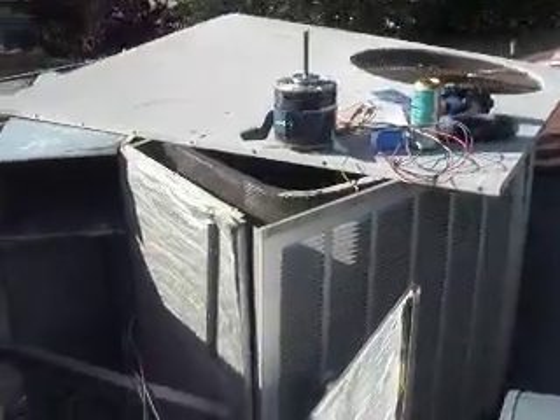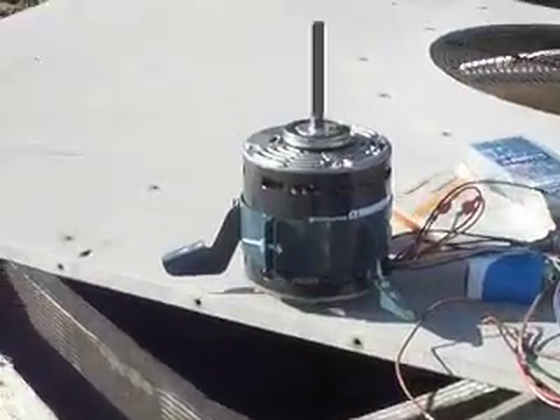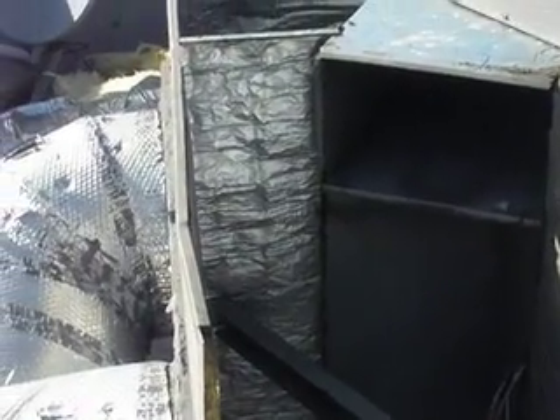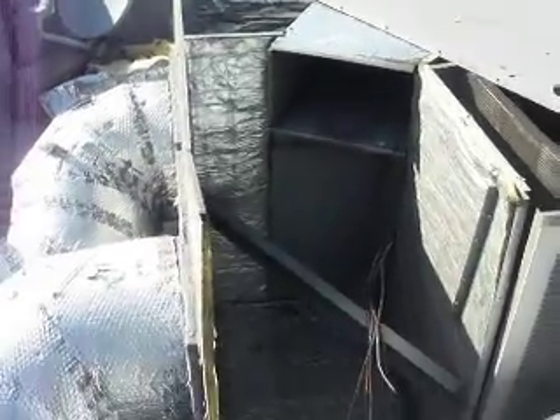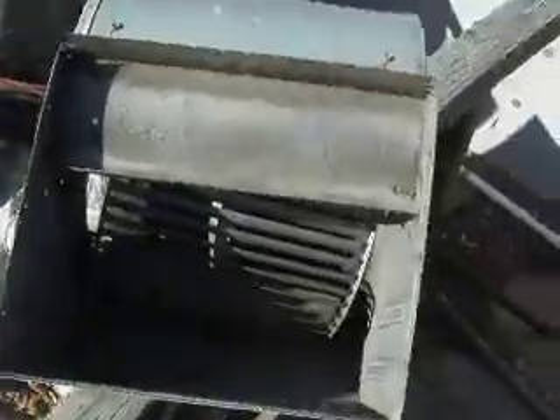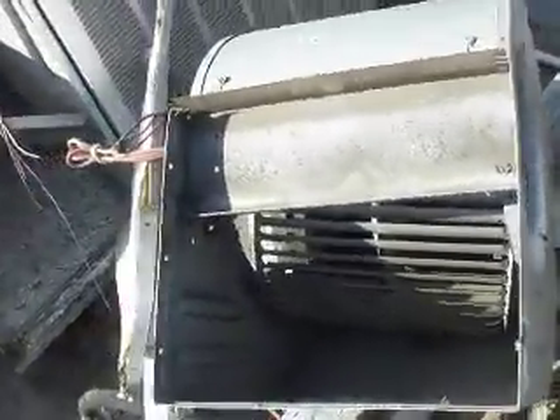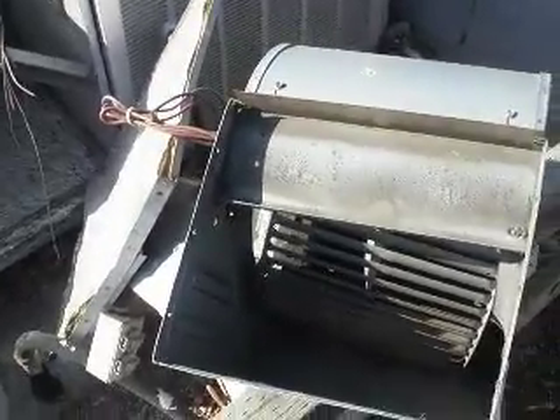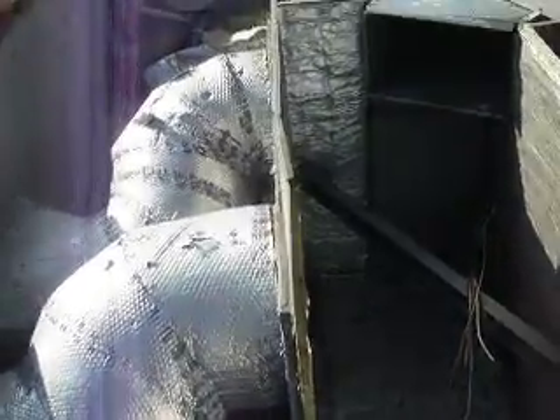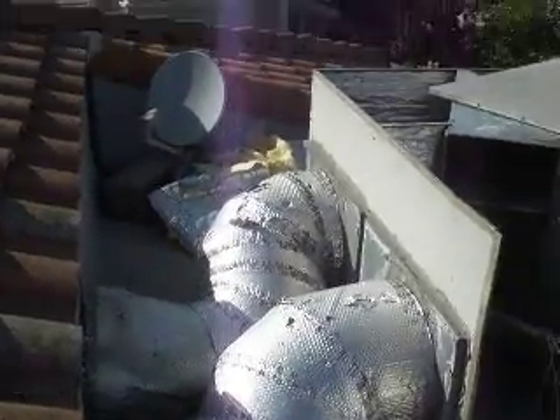We had to go ahead and modify this. It was changed out some years ago, and they did some modifications on the blower motor, using a universal replacement, which actually took off a support bracket that helps support the whole housing. What it did was start to vibrate, which damaged the housing and the bracket and caused other damage. So we went ahead and fabricated some other pieces for this.